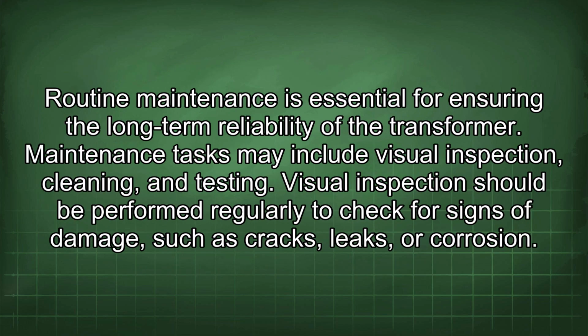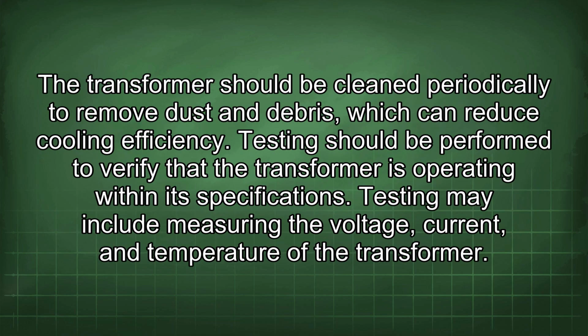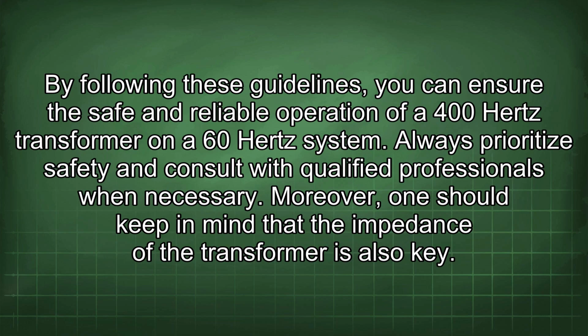Routine maintenance is essential for ensuring the long-term reliability of the transformer. Maintenance tasks may include visual inspection, cleaning, and testing. Visual inspection should be performed regularly to check for signs of damage, such as cracks, leaks, or corrosion. The transformer should be cleaned periodically to remove dust and debris, which can reduce cooling efficiency. Testing should be performed to verify that the transformer is operating within its specifications. Testing may include measuring the voltage, current, and temperature of the transformer. By following these guidelines, you can ensure the safe and reliable operation of a 400 Hz transformer on a 60 Hz system. Always prioritize safety and consult with qualified professionals when necessary.